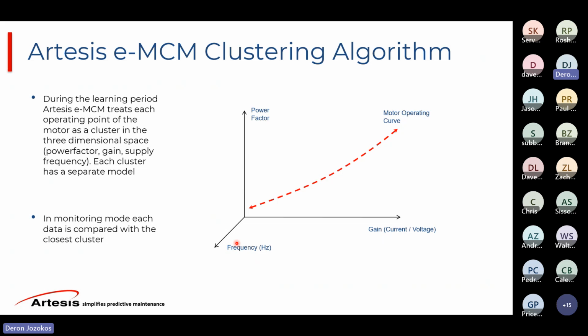Now, after that, it's going to start building these specific math models for that motor and its driven assets. So if you have, say, 2 identical motors and one's driving a pump, that's a very simple system, just on, off, fixed speed, pumping down a tank every time it fills up. And then you have that same exact motor applied to a cooling tower that's constantly hunting around based on outdoor temperatures and loads on the system. You know, they're going to look very, very different electrically. So we cannot apply one algorithm to that specific motor. Say it's a 50 horsepower motor or whatever. Okay, here's that algorithm for that, no matter what it's turning. No, they're going to look very different.